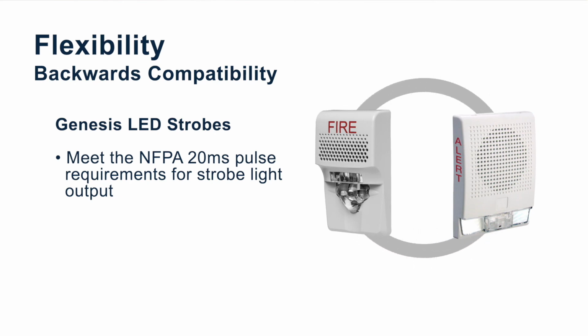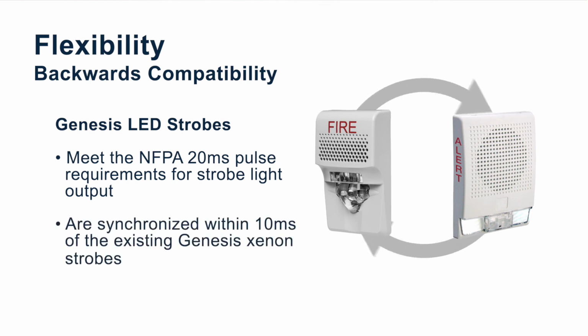The Genesis LED strobes meet the 20 millisecond requirements and are also synchronized within 10 milliseconds of the existing xenon strobes, allowing strobes to be mixed and matched on the same loop and in the same line of sight.